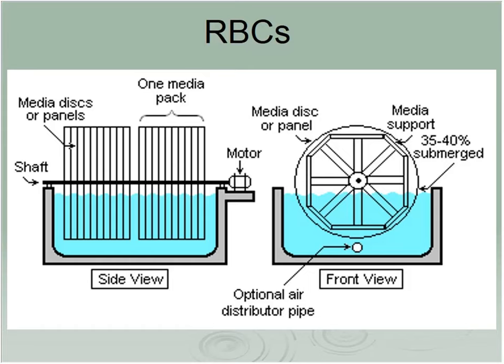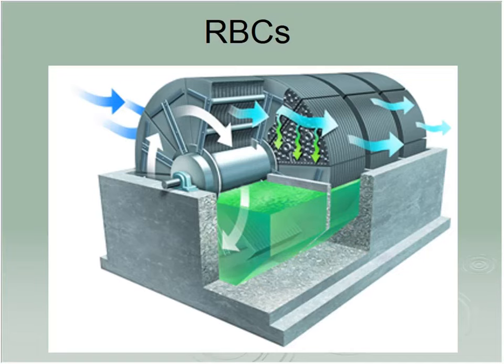Again, they just build that slime on these discs, same as we saw in the trickling filter. On this, though, we really don't have a mechanism for that stuff coming up. It just has to fall out naturally. We have no recirculate or do anything. It's just a simple process. A 25-foot shaft, about 12-foot diameter, probably has 100,000 square foot of surface area on it. You get a lot of surface area. Works pretty well.